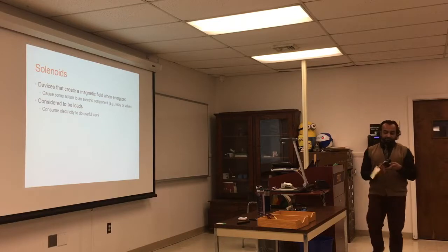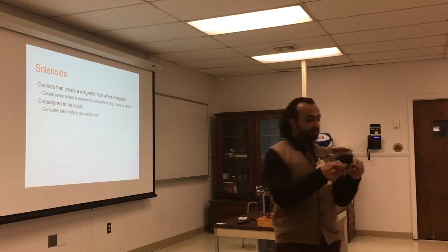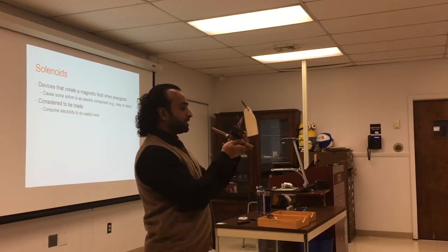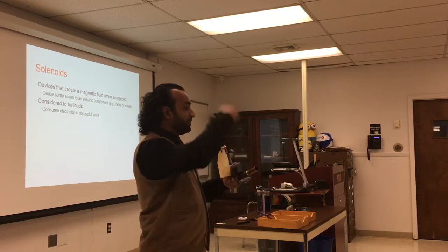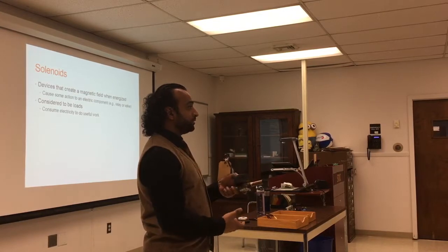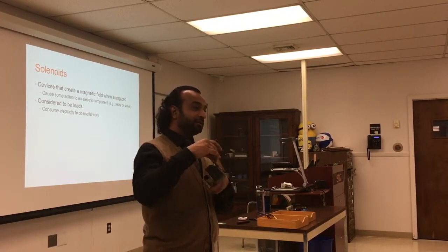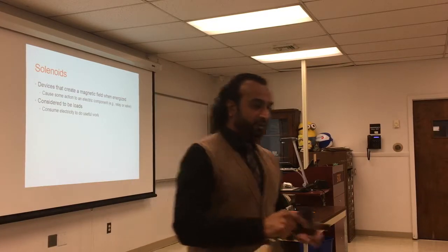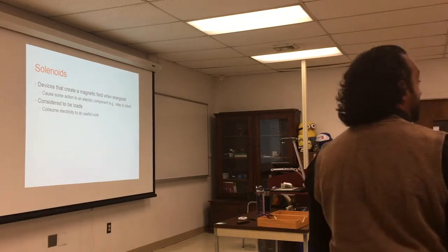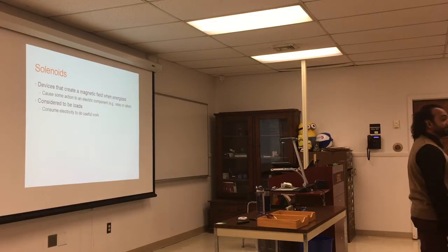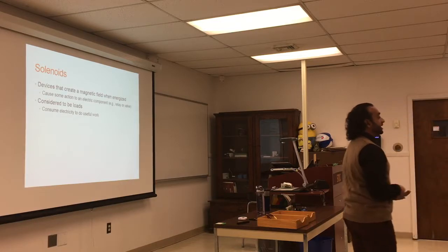So that's a solenoid valve. What does it do? Water goes through it, you energize it, it will either open or close. If you look, it has a coil in it. It pulls out a pin, opens the flow. If it's de-energized, it goes down. And if you can see the wires here, what do they look like? They look like thermostat wire, right? So that's a solenoid valve. Solenoid valves again come in different shapes and prices. Do not skimp on instruments. As we said, the more instruments we have, the more troubleshooting we will do, and we want something that has a lot of reliability.